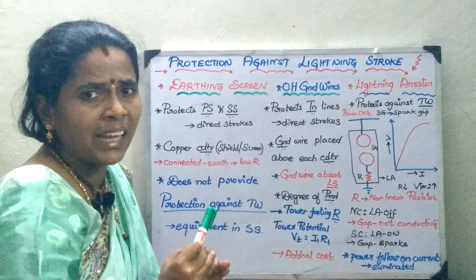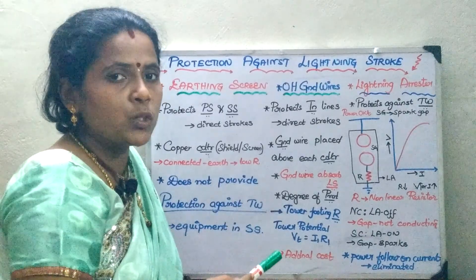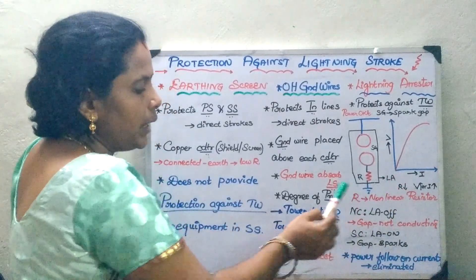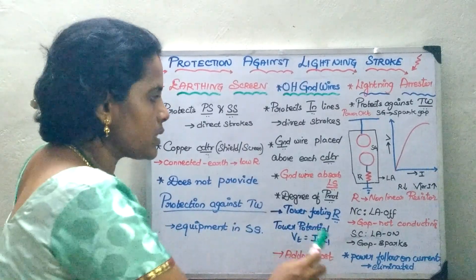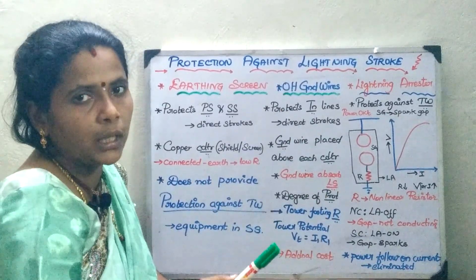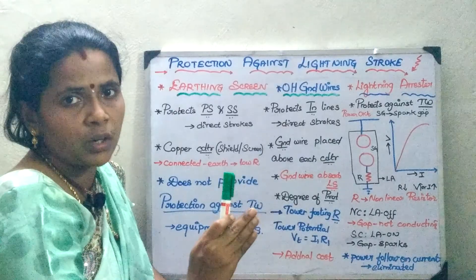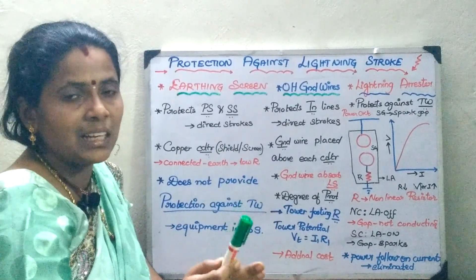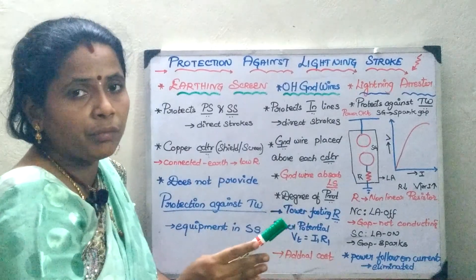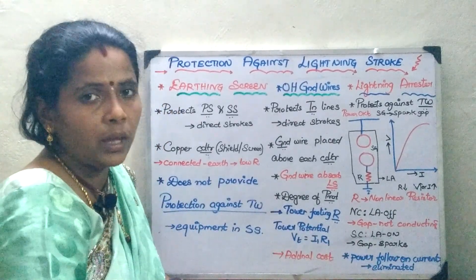The main principle of your lightning arrester is that under normal condition the lightning arrester will be off. Whenever there is a lightning, the lightning arrester will be on and with the voltage increase, through the low resistance path it will get drained to the ground. One drawback to note is that after the lightning is over, you still have a current of 10 kilo-amps or 15 kilo-amps still flowing in the circuitry. This is called the power follow-on current, which is a high magnitude of current that should not penetrate as it can damage your equipment. This power follow-on current should be eliminated as soon as possible.